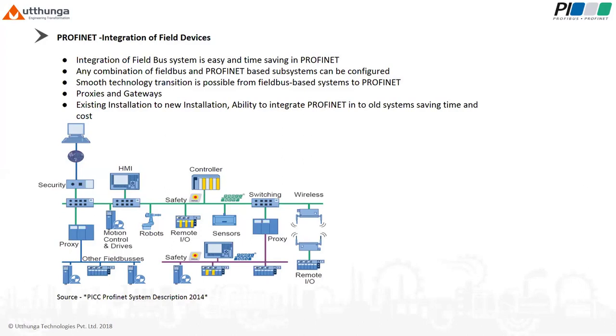In some cases, a plant owner would like to be able to integrate an existing installation into a newly installed PROFINET system easily. Plant and machine manufacturers would like the ability to use their proven and familiar devices without any modification for PROFINET automation projects. And device manufacturers would like the ability to integrate their existing field devices into a PROFINET system while reducing the cost. This will be very easy in a PROFINET system. Using proxies, device couplers, and gateways, we can integrate any other fieldbuses.